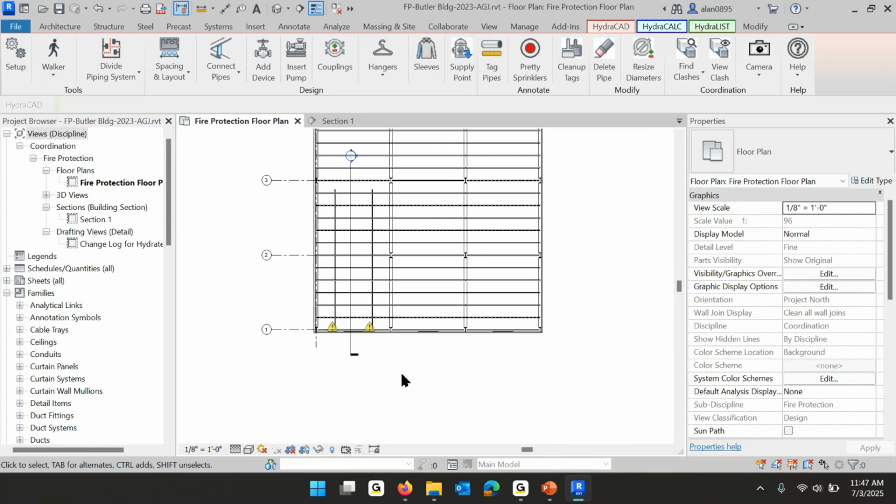But it's probably better to say top of structure, and the structure that it's looking for is a roof or a floor. So from wherever it's going to put a sprinkler, it says, oh, here's a good place to put a sprinkler. Let me look up until I bump into a roof or a floor. And then I'm going to measure down 1'2" from that. And it'll be from the bottom of the floor or the roof? Yes. Okay.